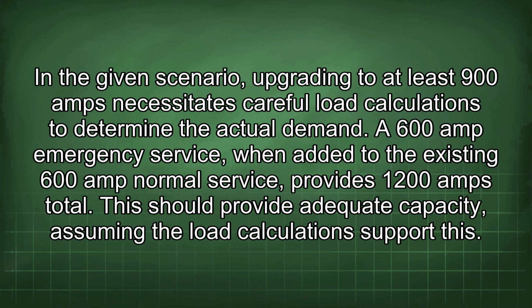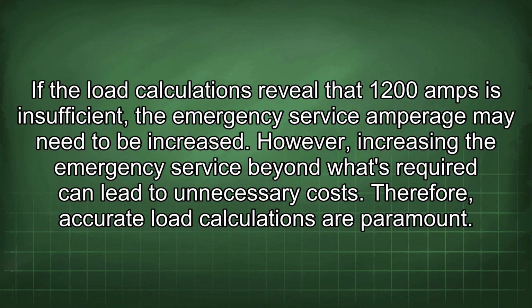In the given scenario, upgrading to at least 900 amps necessitates careful load calculations to determine the actual demand. A 600 amp emergency service, when added to the existing 600 amp normal service, provides 1200 amps total. This should provide adequate capacity assuming the load calculations support this. If the load calculations reveal that 1200 amps isn't sufficient, the emergency service amperage may need to be increased. However, increasing the emergency service beyond what's required can lead to unnecessary costs. Therefore, accurate load calculations are paramount.